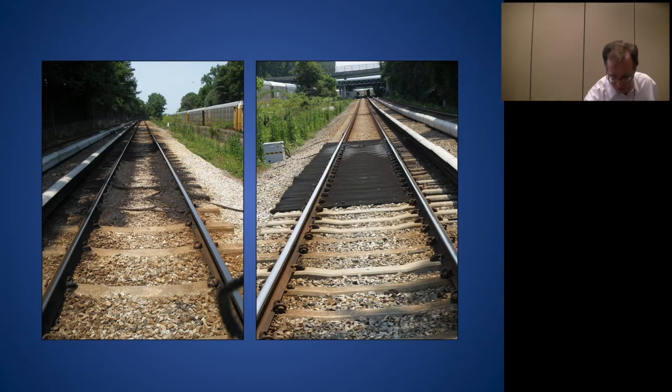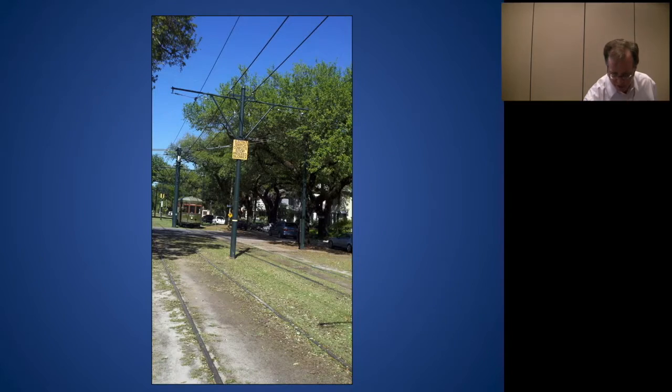And this next one, you're going to see why I don't like that pretty green grass track. This is what it looks like whenever it gets older. Okay, this is New Orleans. Okay, that's been in the ground for a while. That at one time had some rubber boots around it, but you can see that that's low resistance track.